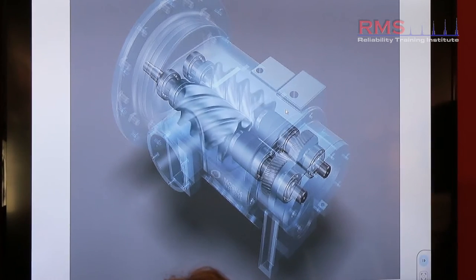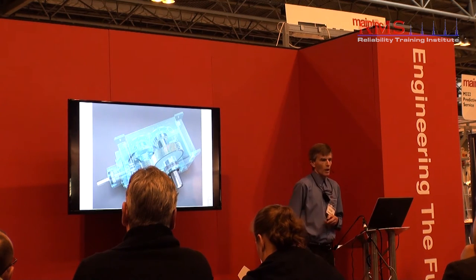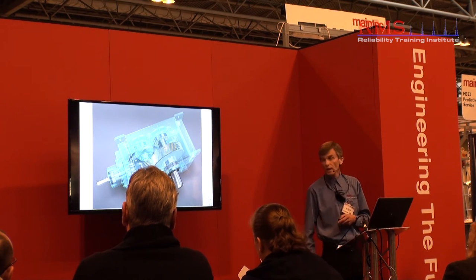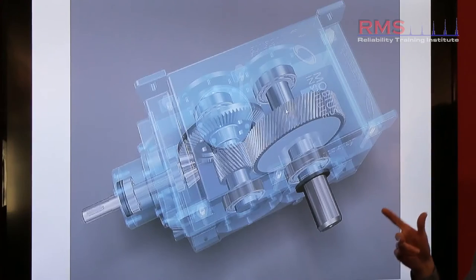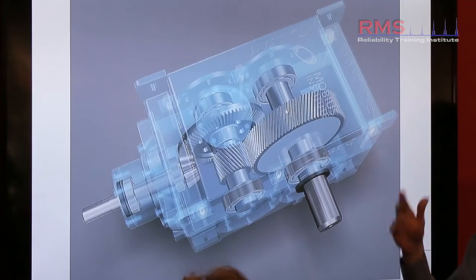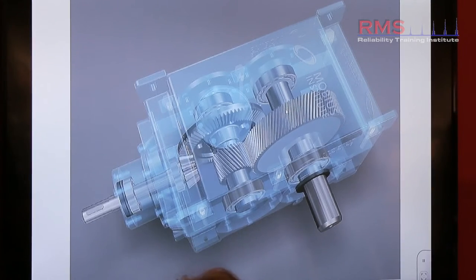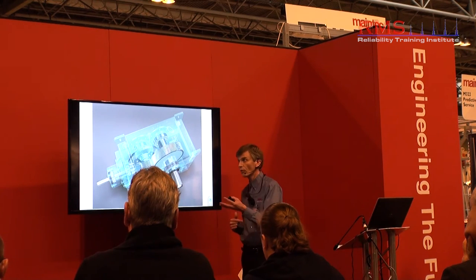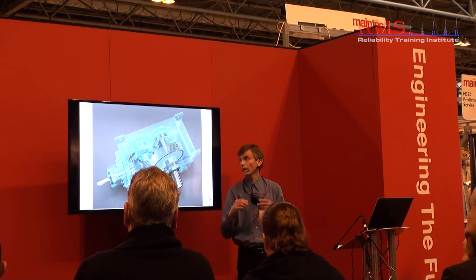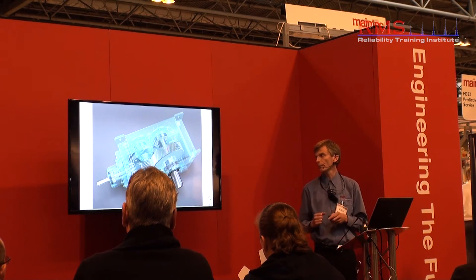If there are four screws, four heartbeats per rotation. Each gear will have a certain number of teeth, and a defect on one of the teeth, or all of the teeth, or some of the teeth — the heartbeat pattern will be distinctly different to what we saw before, where the machine was misaligned, or what we saw with the volutes or the blades on the pump.